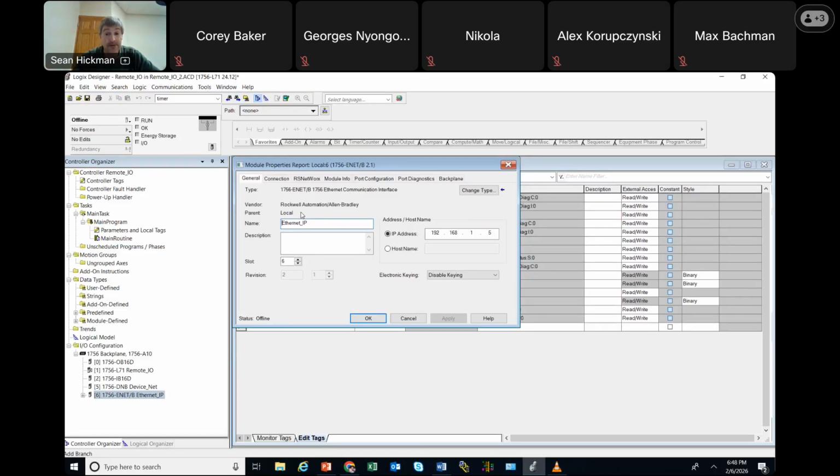You're using 28. So if you were to try and bring in one of the new bridges, like EN3TR or 4TR, this thing would freak out. It would say it doesn't know what it is. It's too new. The software came out before that bridge came out and was offered to the public. But my computer works really good with this stuff because I have version 37 on my computer and 36 and 35 and 34 all the way down to 21. So when I try to install a bridge EN3TR or 4TR, my computer knows what it is. Yours might not, depending on how high of a software revision that you have.